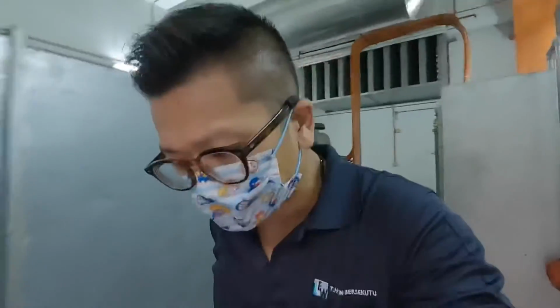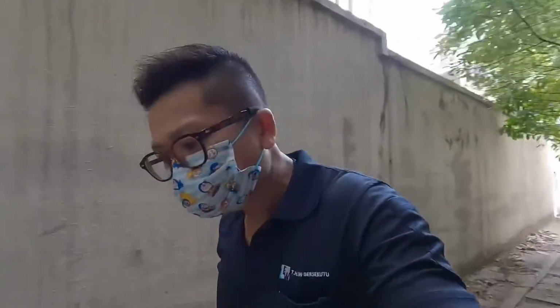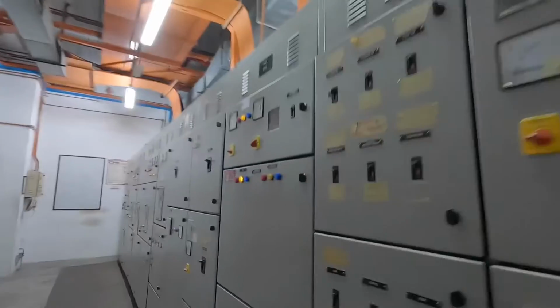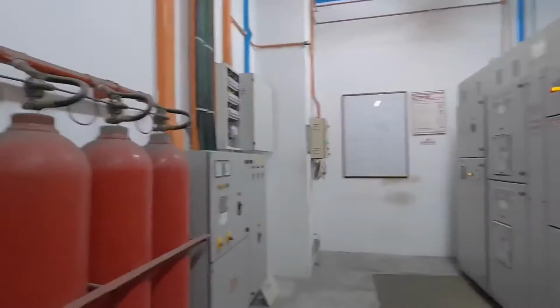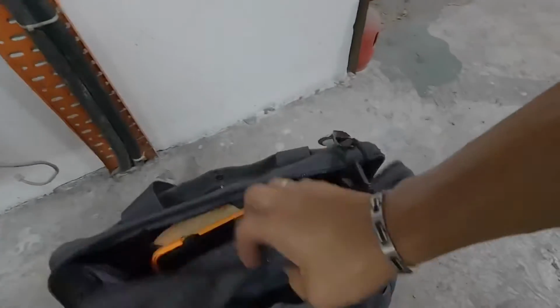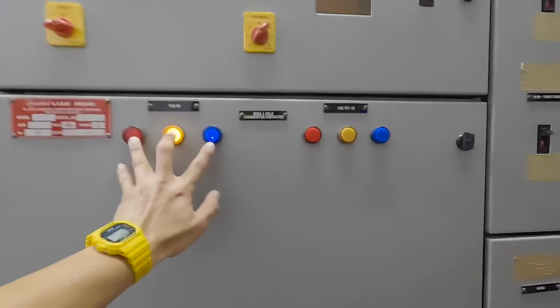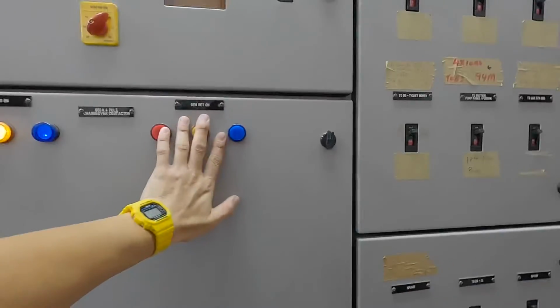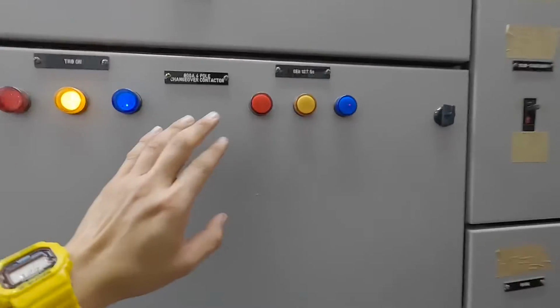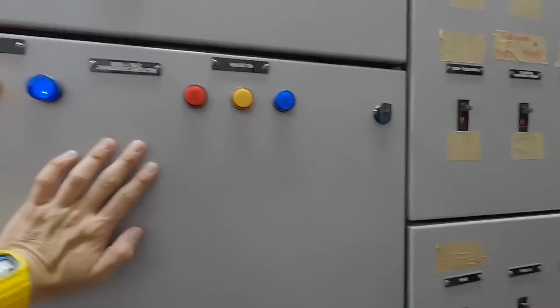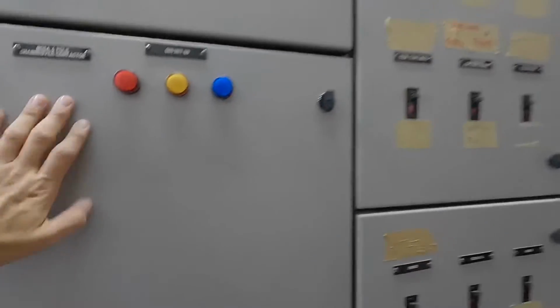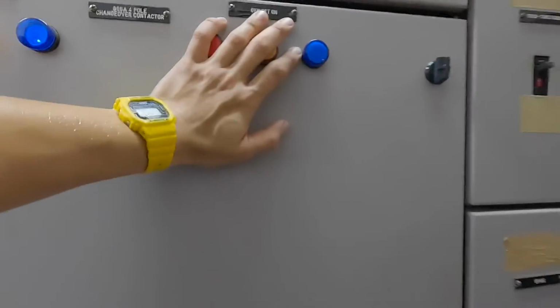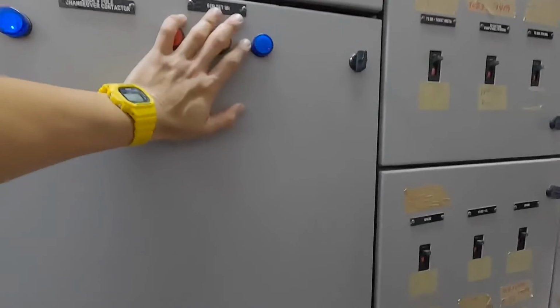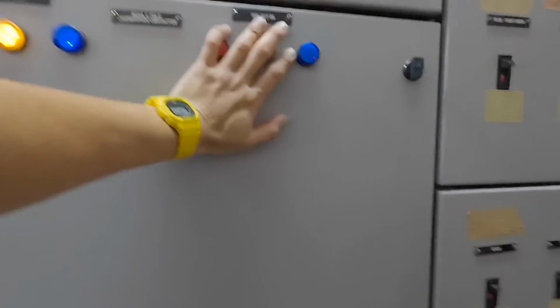Let's go to the LV room. Okay, here we have the LV room. Let me take the jumper wire. Alright, this is the ATS panel. Currently, TNB power supply is on, genset is off. We're going to simulate a TNB power interruption by jumping two contacts, which are normally closed contacts. By jumping that wire, it will give a signal for the genset AMF panel to start the genset automatically. As I release the jumper wire, it will initiate a shutdown of the genset in about 4 to 5 minutes.